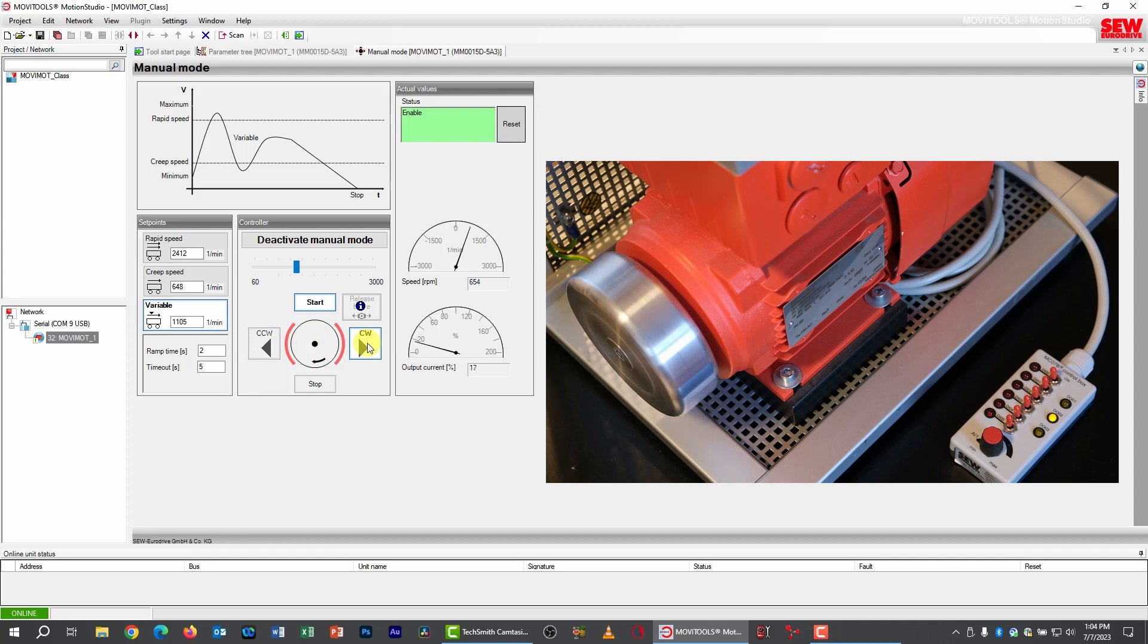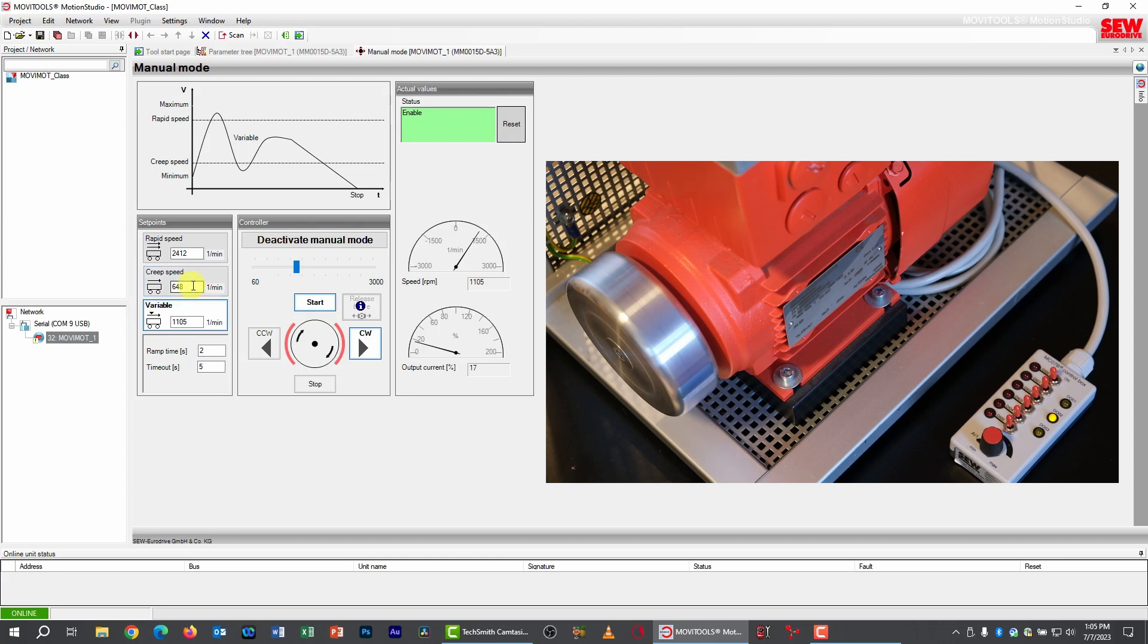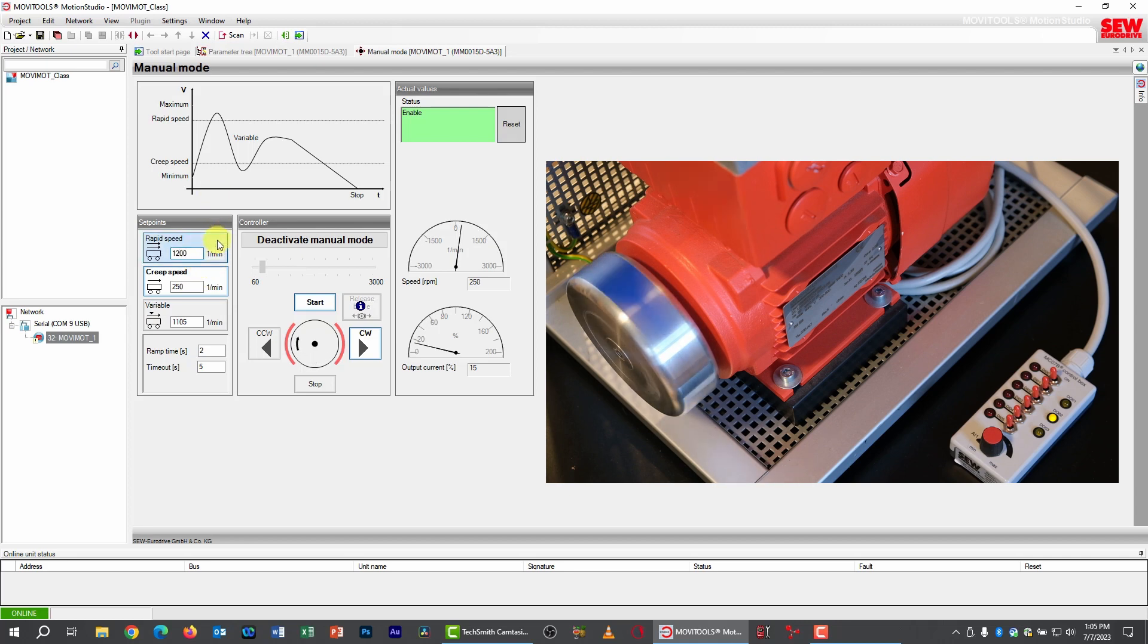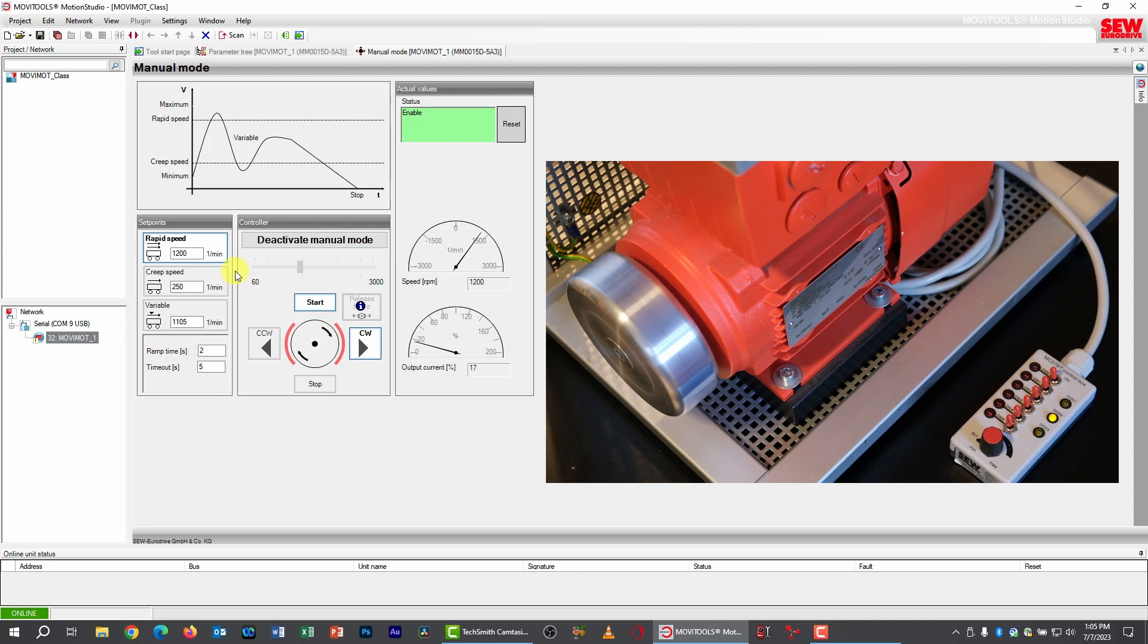And I'll go back to clockwise. And if you want to go to one of the fixed speeds, you can click its button. For example, creep speed goes at 648 RPM. That's kind of an oddball value. Let's change that to something more typical. I'll change it to 250 RPM, and then we'll click the creep speed button, and that will slow the drive down. Let's set our rapid speed to 1200 RPM and click that, and that goes at a higher speed.